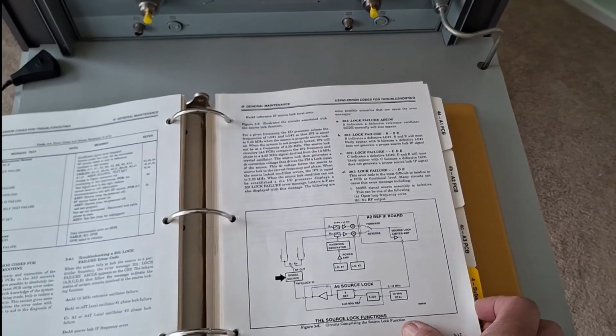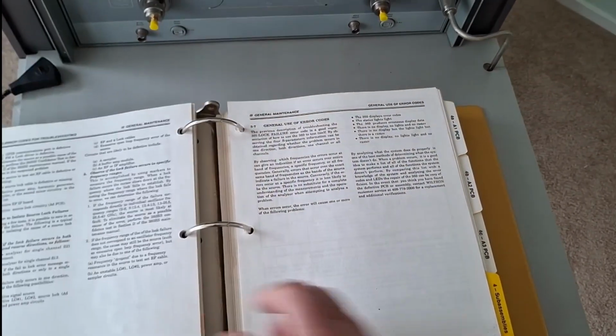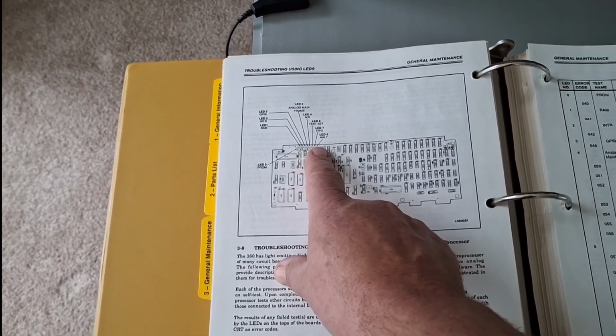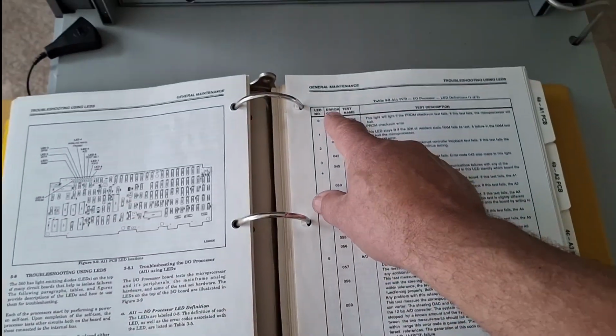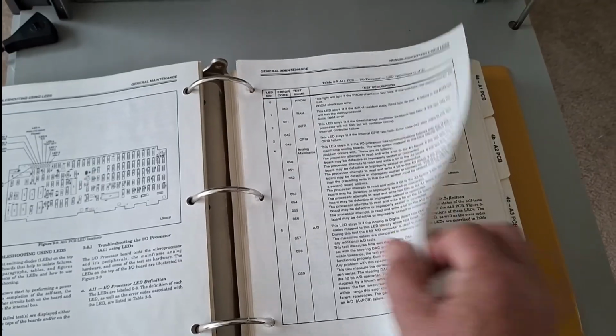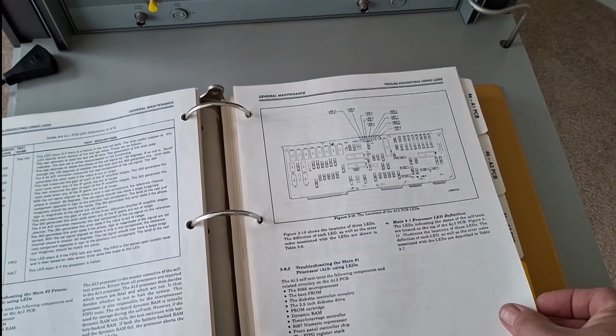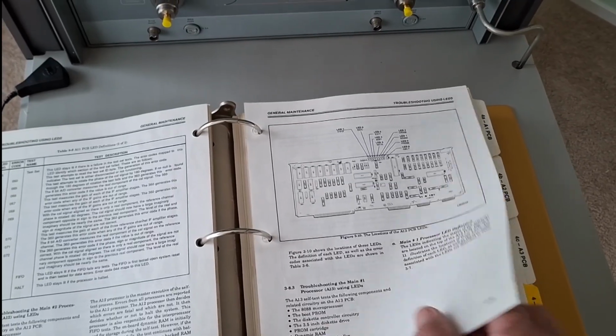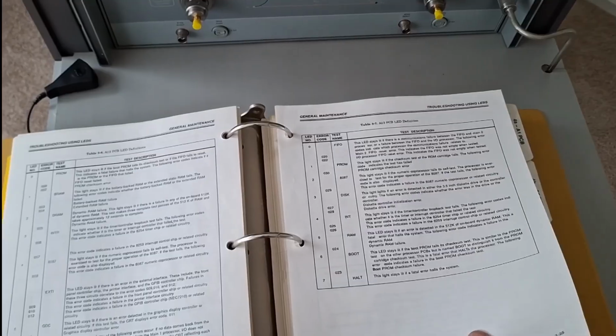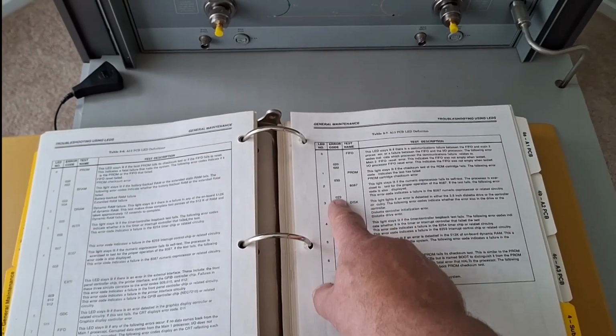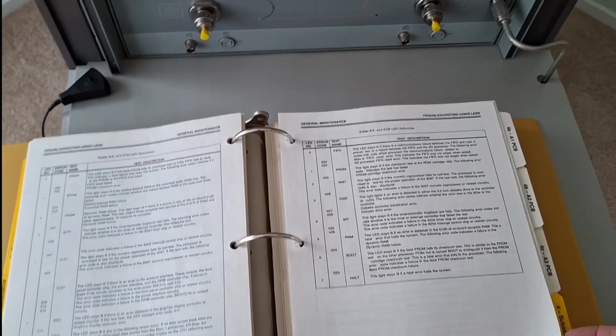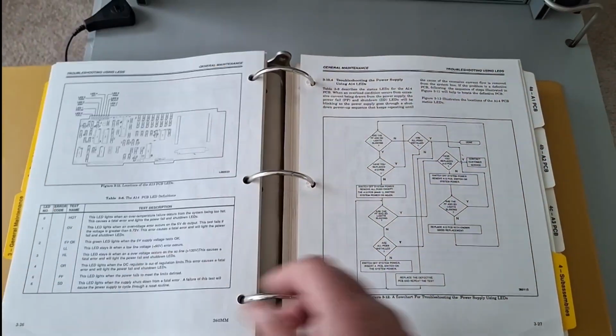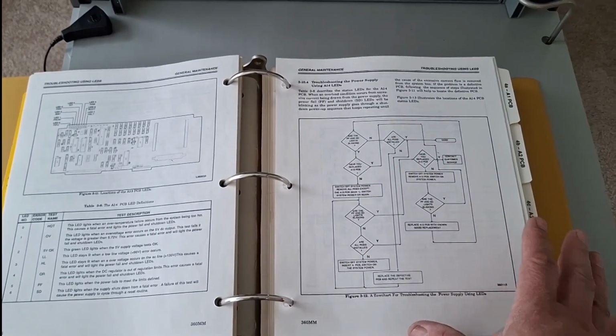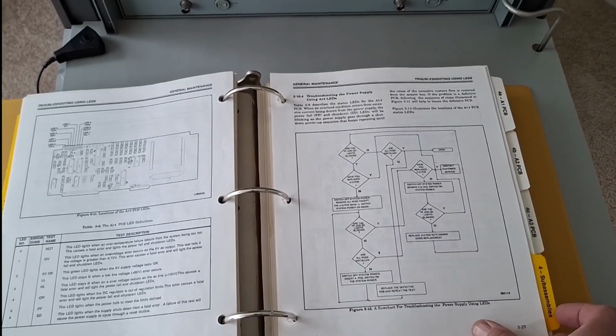Not only are there error codes that come up on the CRT display, but there are also LEDs that are positioned on the edge of each card. And these LEDs indicate also what errors and what faults exist or have been detected on those PCBs. And again, there are pages and pages of LEDs, their corresponding error codes, and the test description, what exactly they're testing for. So all extremely helpful. This is combined with flow diagrams, flow charts for troubleshooting power supplies, which is something that I need to look at, and so it goes on.